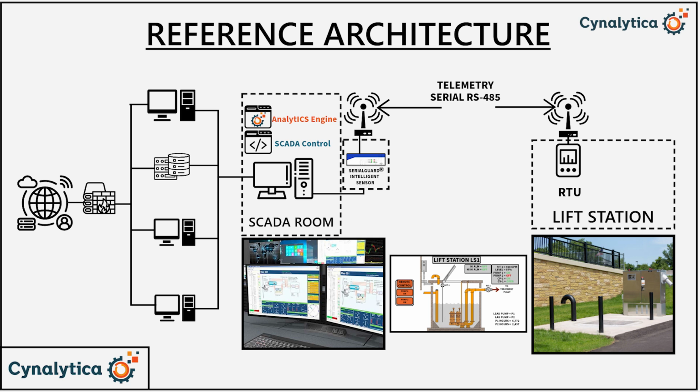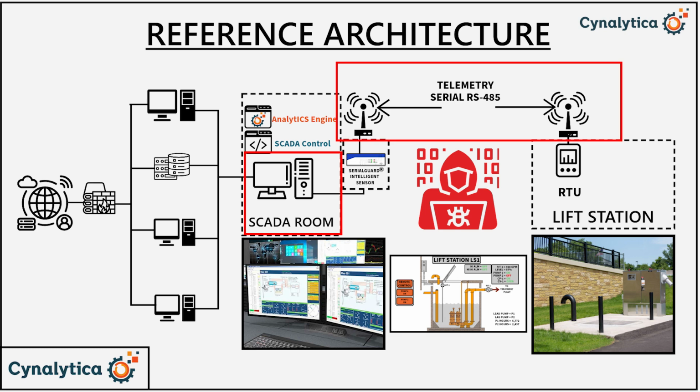In this final threat scenario, an attacker has again gained access to the SCADA control station and/or the telemetry network and has either disabled the polling interval in the SCADA station, meaning that the SCADA station is no longer requesting updates and that its screen most likely is in a static state. Nothing is changing. So from an operator perspective, it would look like everything was normal.